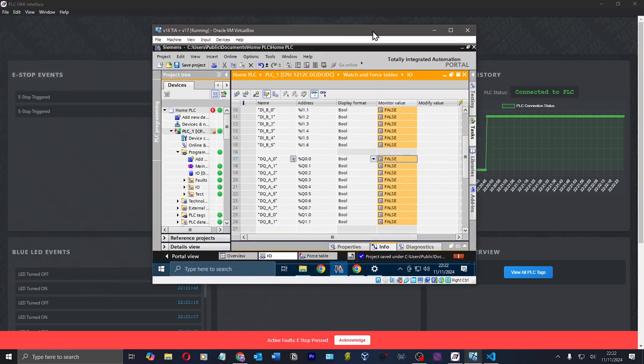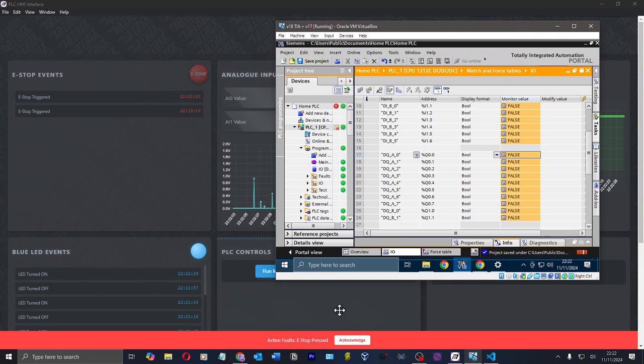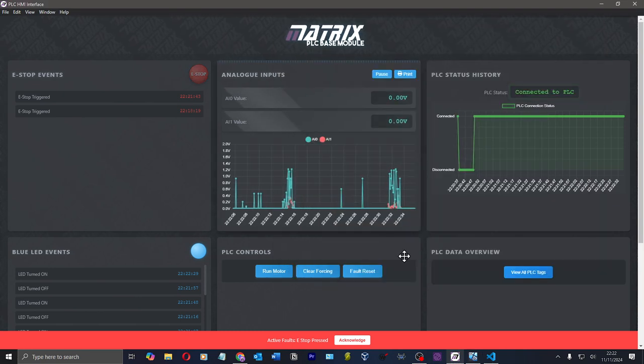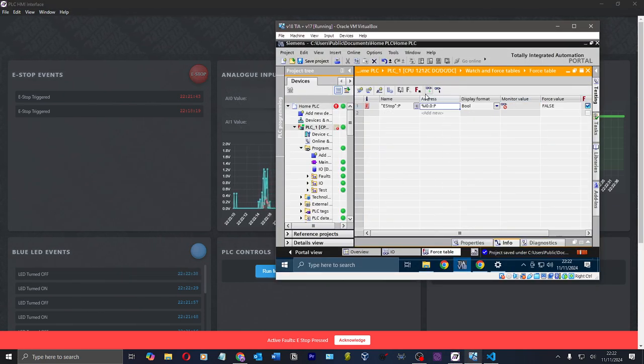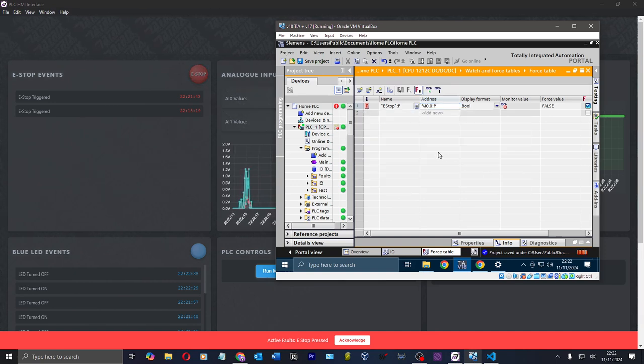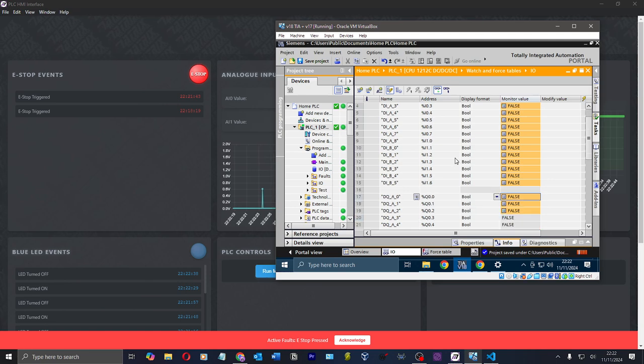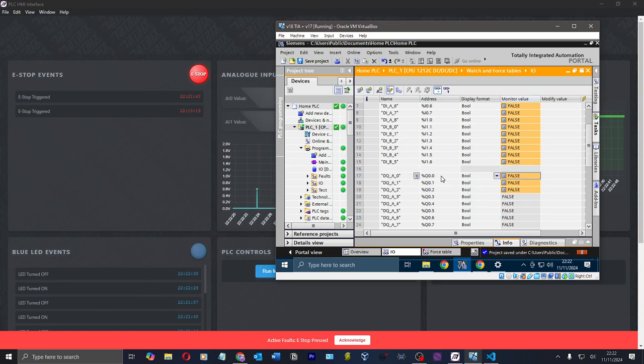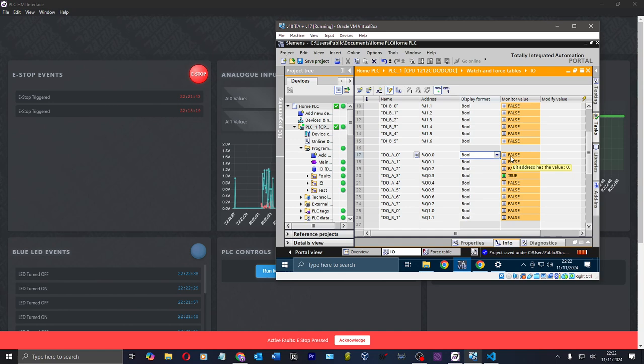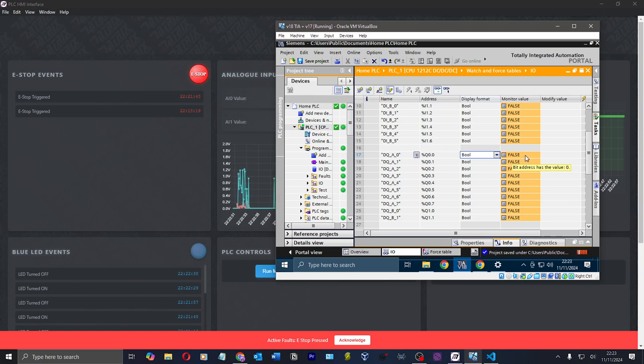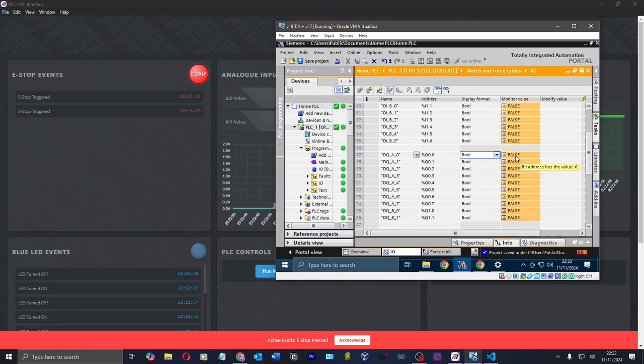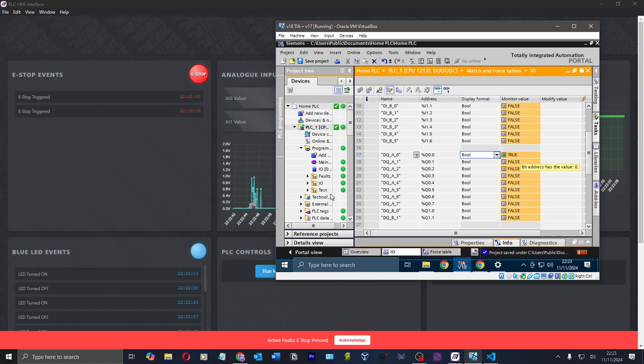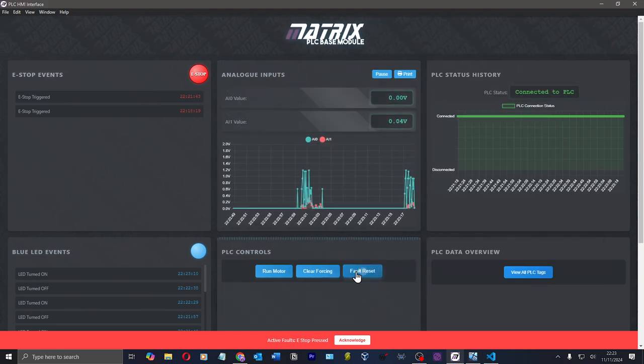DQ A0. Why is that not, the LED is turning on and off, isn't it? It's because the e-stop's pressed. So let's stop forcing. So the e-stop's healthy. Then we'll see the LED turn on and off. Because I check my e-stop before I turn on my outputs. I forgot what I wanted to do now. I can turn on this DQ here. So DQ 1 is currently false. If I click run motor, that number comes true. If I click it again, that becomes false.